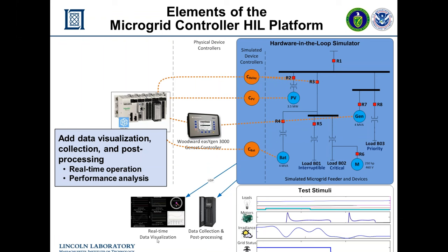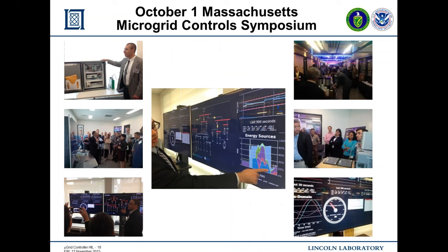We added real-time visualization, data collection, and post-processing to compare performance between microgrid controllers on our testbed using hard metrics. On October 1st, we used this HIL platform as the centerpiece of the Massachusetts Microgrid Control Symposium, running both Schneider and Eaton microgrid controllers through a 15-minute test sequence, both on-grid and off-grid — demonstrating power factor control, islanding with non-critical load shedding, controlling the genset, PV, and battery while maintaining a voltage profile.